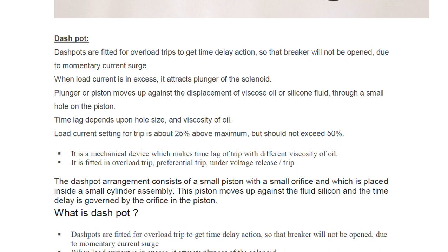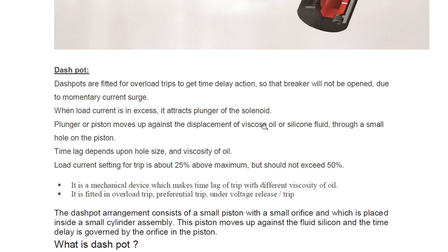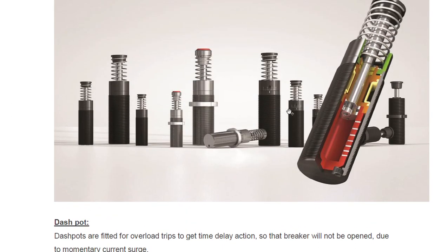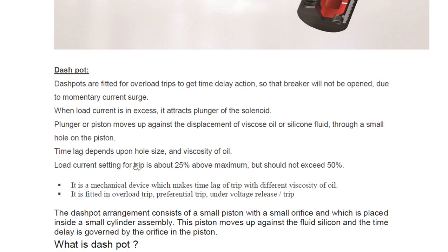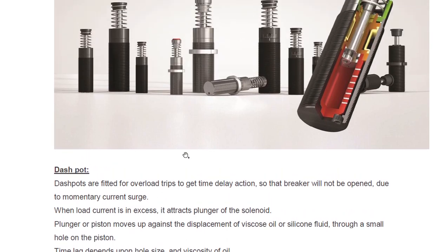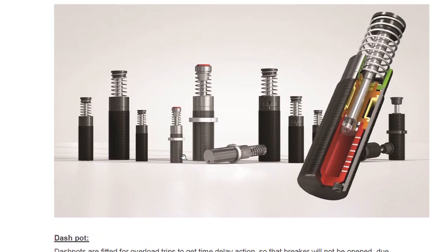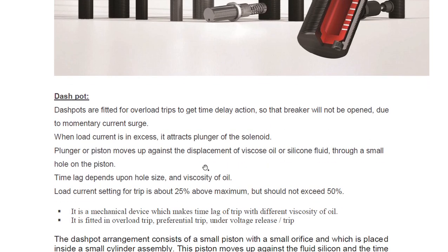Dashpot is a safety device. When load current is in excess, it attracts the plunger to the solenoid. The plunger or piston then moves up — as you can see in the diagram. The plunger or piston moves up against the displacement of viscous oil or silicone fluid through a small hole on the piston. There is a small hole provided on the piston, which may not be clearly visible in this diagram.